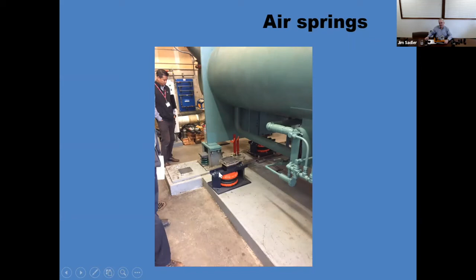But they had terrible noise in the space below. So they replaced the steel springs with air springs, and this is during that transition. And this is one of the rare instances where we begged the acoustician to provide before and after results, and they were able to do that. As you can appreciate, usually when you solve a noise problem, there's not much enthusiasm for doing a follow-up test. But in this case, we got it.